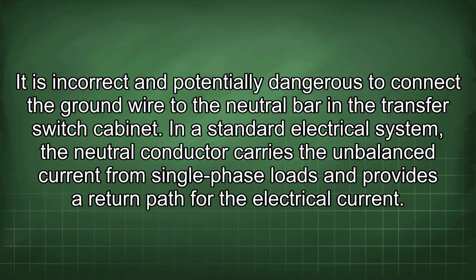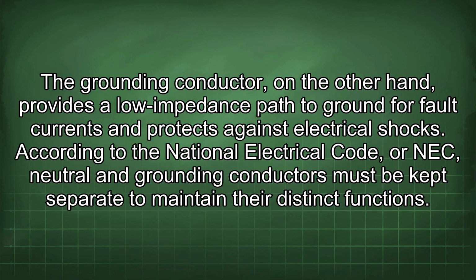It is incorrect and potentially dangerous to connect the ground wire to the neutral bar in a transfer switch cabinet. In a standard electrical system, the neutral conductor carries the unbalanced current from single-phase loads and provides a return path for the electrical current. The grounding conductor, on the other hand, provides a low-impedance path to ground for fault currents and protects against electrical shocks.